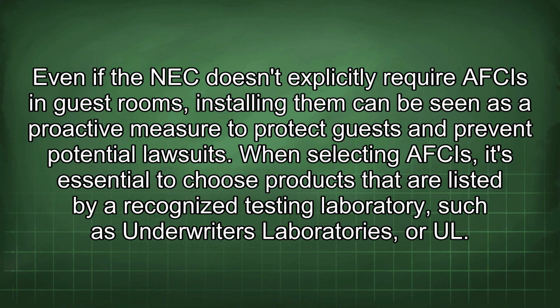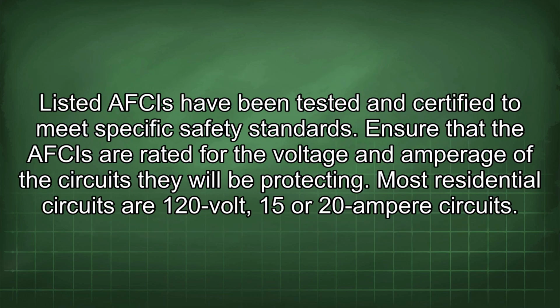When selecting AFCIs, it's essential to choose products that are listed by a recognized testing laboratory, such as Underwriters Laboratories, or UL. Listed AFCIs have been tested and certified to meet specific safety standards. Ensure that the AFCIs are rated for the voltage and amperage of the circuits they will be protecting. Most residential circuits are 120 volt, 15 or 20 ampere circuits.